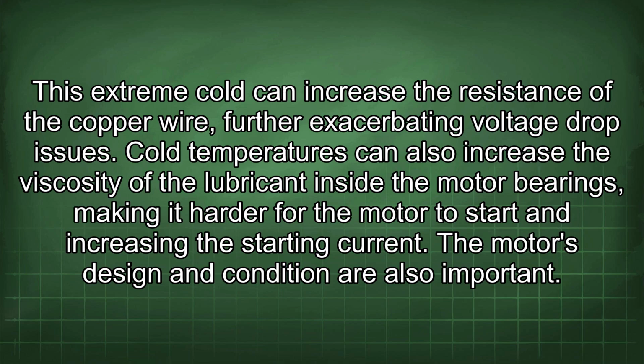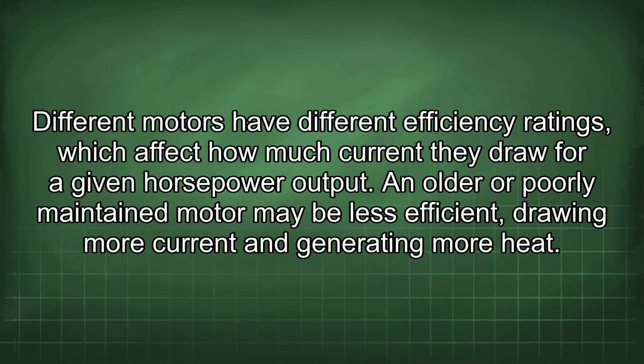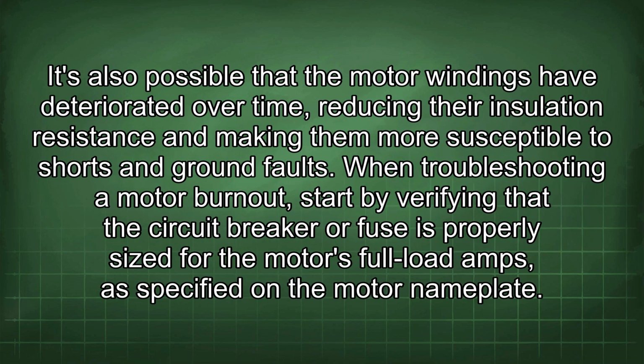The motor's design and condition are also important. Different motors have different efficiency ratings, which affect how much current they draw for a given horsepower output. An older or poorly maintained motor may be less efficient, drawing more current and generating more heat. It's also possible that the motor windings have deteriorated over time, reducing their insulation resistance and making them more susceptible to shorts and ground faults.